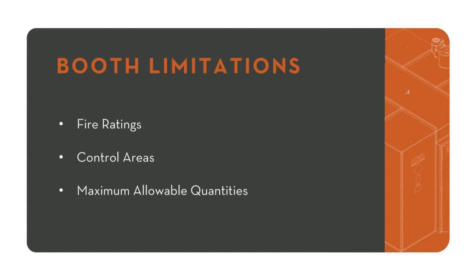But what if you need more than 600 pounds in your entire facility? If you need to utilize more than 600 pounds in your entire facility, you're going to need to utilize multiple control areas. Placing a couple of unrated, like not fire rated, booths together does not give you separate control areas. So having a 1 hour fire rated unit would be a lot easier, because then they would all be separate control areas. It's not an impossible hurdle to get over for modular units, but it does add quite a bit of money. So from what I've seen, when people run into the issue of fire ratings, they tend to think about going down a different avenue, but it's certainly something that extraction booths can accommodate, but it's generally one of those initial limitations.